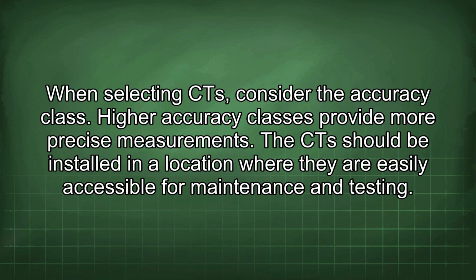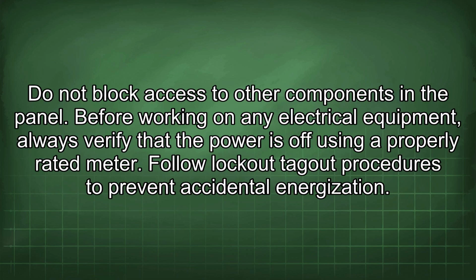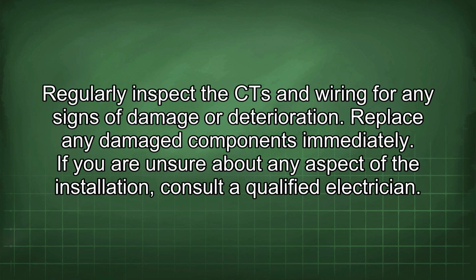The CT should be installed in a location where they are easily accessible for maintenance and testing. Do not block access to other components in the panel. Before working on any electrical equipment, always verify that the power is off using a properly rated meter. Follow lockout-tagout procedures to prevent accidental energization. Regularly inspect the CT and wiring for any signs of damage or deterioration. Replace any damaged components immediately.